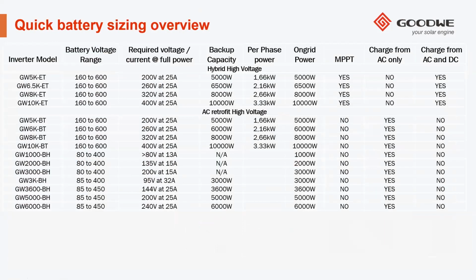Then lastly, I just have a little breakdown of the required battery voltages for the high voltage batteries. With the inverters and the limitation of current, I would just like to highlight this for a lot of the installers. Once we're moving over to use a lot of the high voltage batteries, this is something we need to pay quite close attention to. Because we are limiting our inverters' current at a low current of 25 amps on the ETs, for a 10 kilowatt inverter to give you 10 kilowatts of backup, you will need a minimum of 400 volts. So if the customer is installing a 10 kilowatt and wants to use the backup to a maximum, he needs to ensure that the battery bank is of sufficient capacity to give the required voltage.